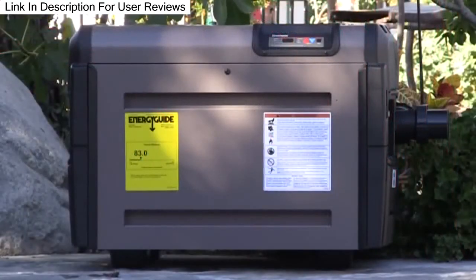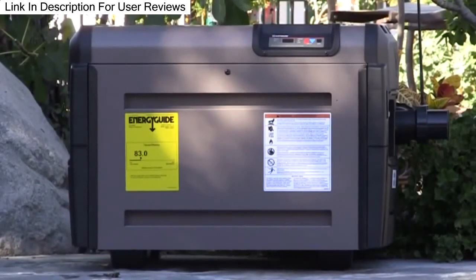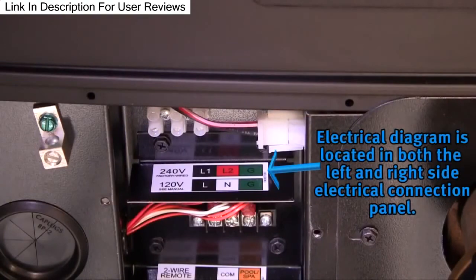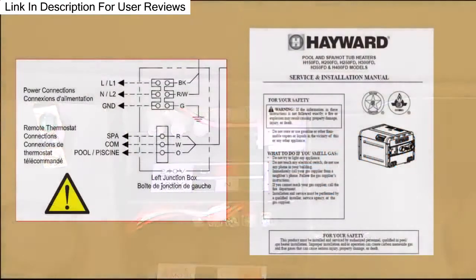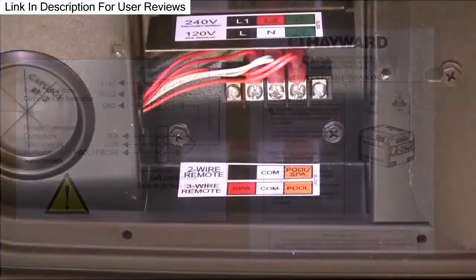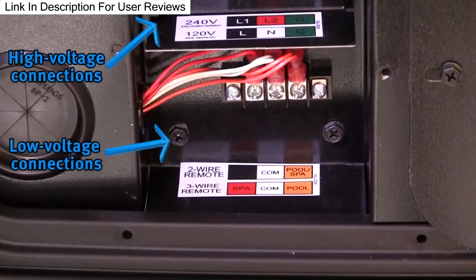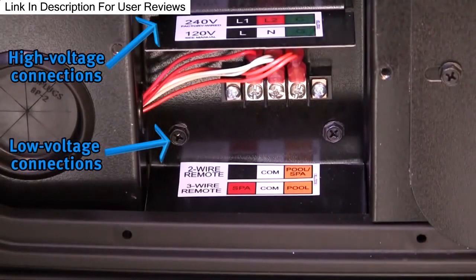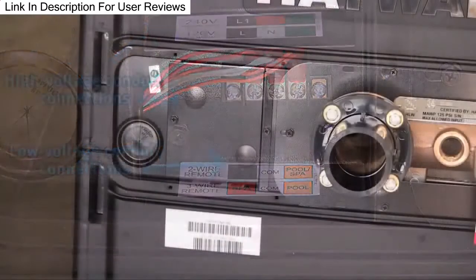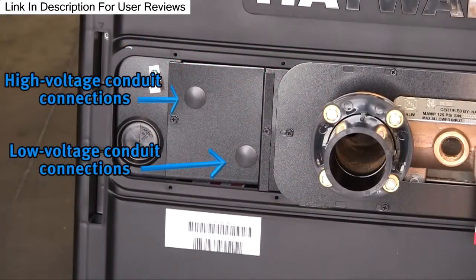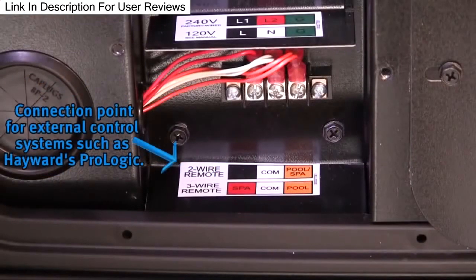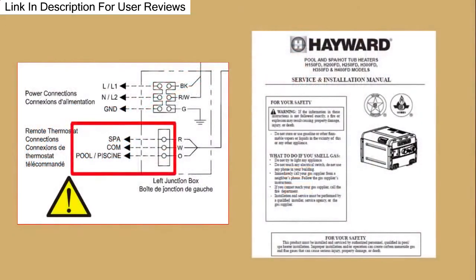Wiring of the heater for high voltage can be accomplished from either the left or right side of the heater. Wire the heater according to the wiring diagram located in the heater and also in the installation manual. If the heater is to be automated by an external control system, such as Hayward's ProLogic, connections for the controller are made in the same panel as the main power. Low voltage wires must be run in their own conduit. Make connections per the wiring diagram located in the electrical connection panel and the installation manual.